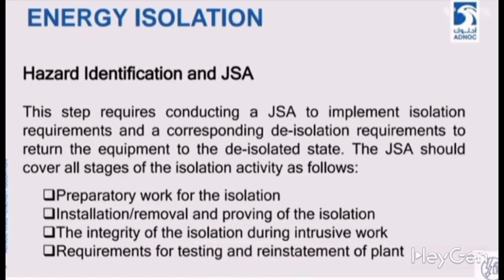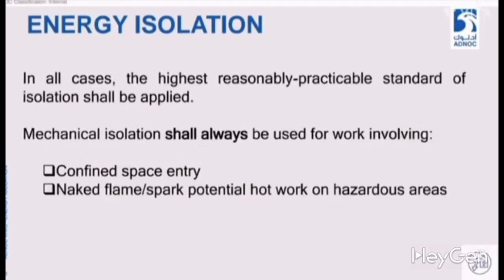When we have completed all our work and need to hand over the plant after the isolation, we must also consider that no isolation remains blind there, which could be dangerous for our process or work. Therefore, all such hazards and things must be considered within our job safety analysis, including all processes and steps of isolation. It should be ensured that its control measures are properly communicated. For energy isolation, the highest reasonably practicable standard of isolation should be used in all cases.